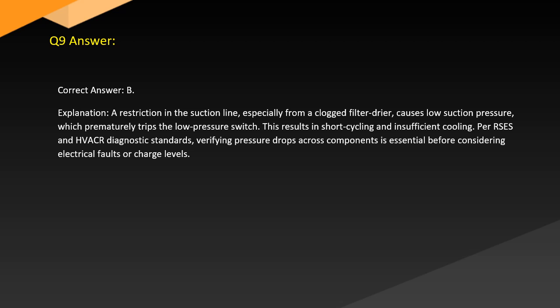Answer. Correct answer: B. Explanation. A restriction in the suction line, especially from a clogged filter dryer, causes low suction pressure, which prematurely trips the low-pressure switch. This results in short cycling and insufficient cooling. Per HVACR diagnostic standards, verifying pressure drops across components is essential before considering electrical faults or charge levels.